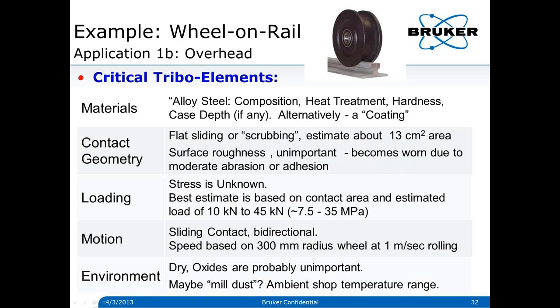Here is example 1B — also wheel on rail, but a little different. This is a low-speed overhead crane, often used in steel mills and large production facilities. With independent motors driving the left and right sides, it's very hard to keep them synchronized precisely, so you get a ratcheting or scrubbing back and forth of the left and right side wheels. That's why there's a double-flanged wheel — they scrub on the rail. The duty cycle on the wheel is only about 15-20%, since each time the wheel goes around it's only in contact at the bottom.